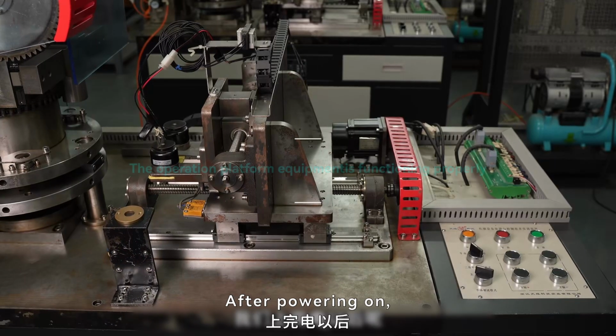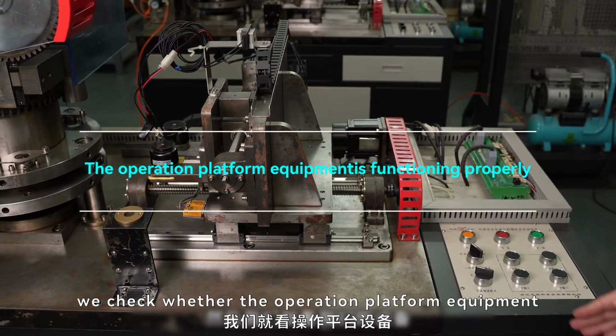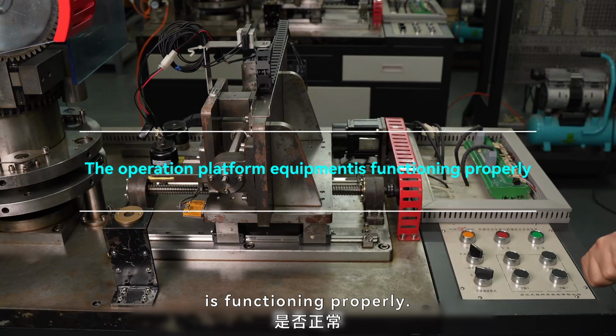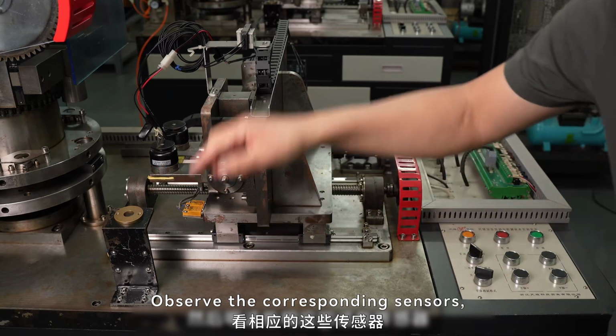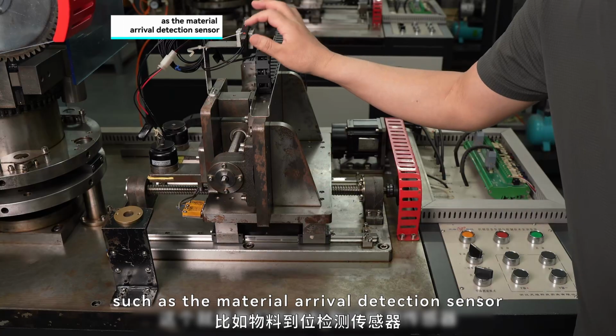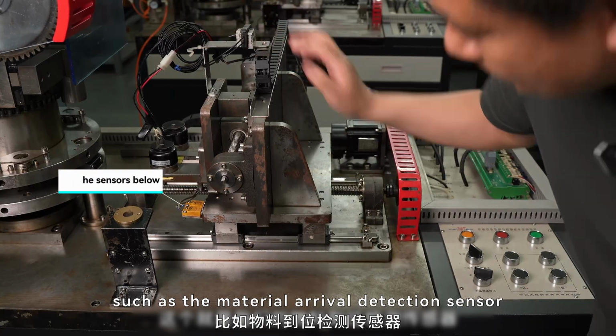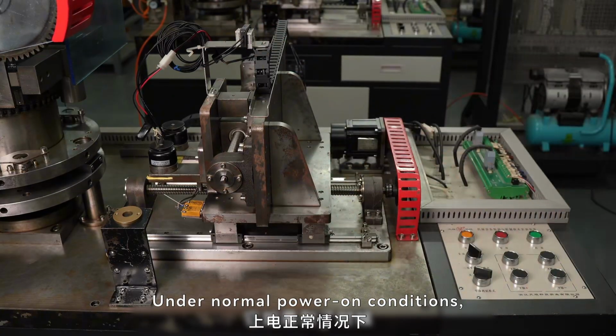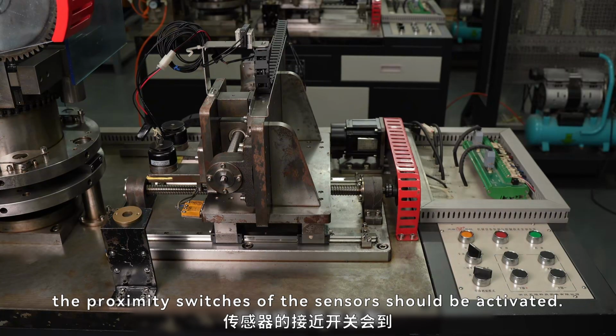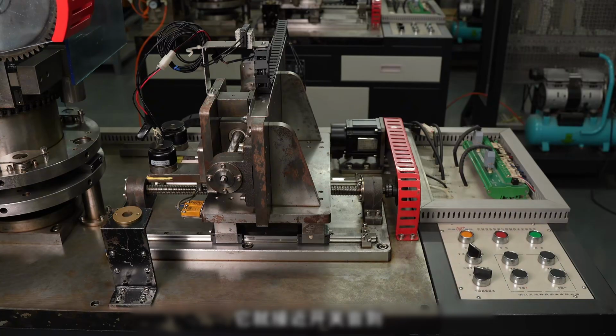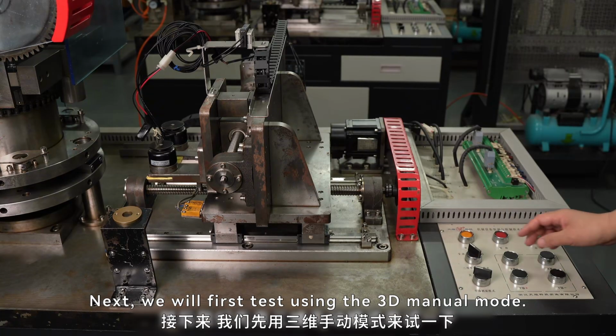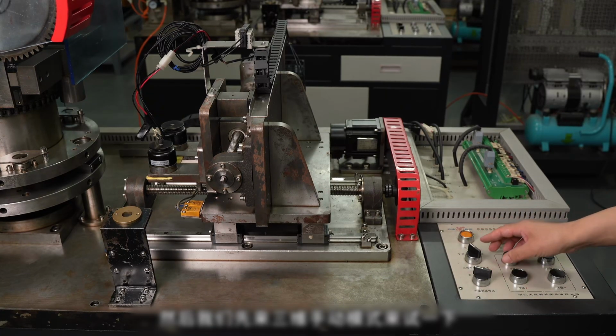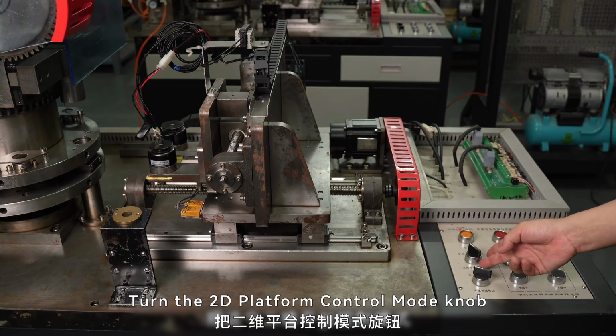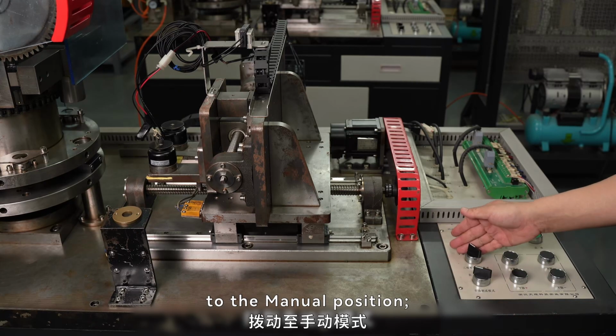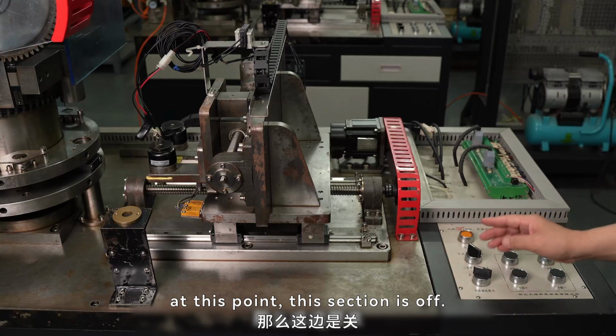After powering on, we check whether the operation platform equipment is functioning properly. Observe the corresponding sensors, such as the material arrival detection sensor and the sensors below. Under normal power-on conditions, the proximity switches of the sensors should be activated. Next, we will first test using the 2D manual mode. Turn the 2D platform control mode knob to the manual position. At this point, this section is off.